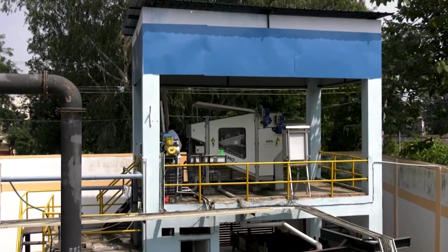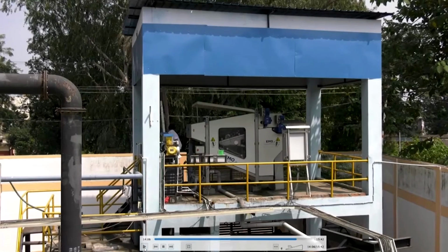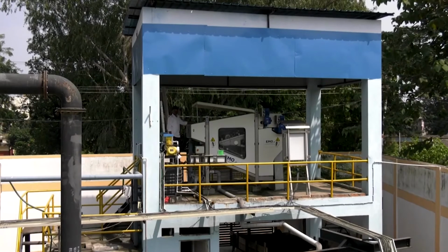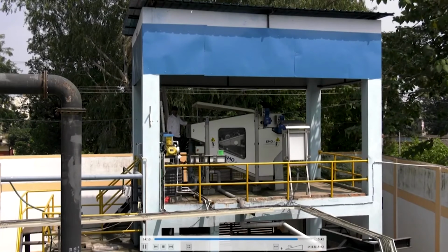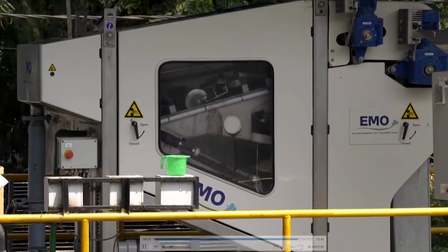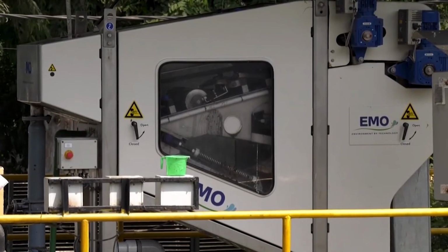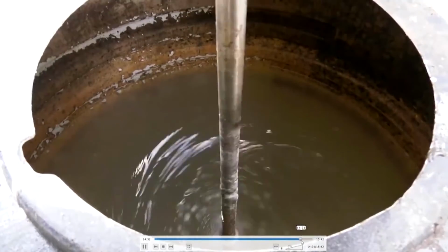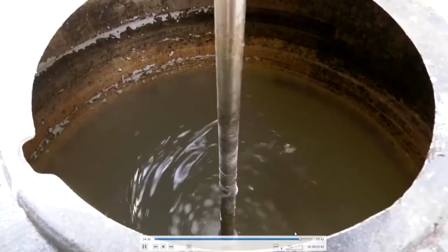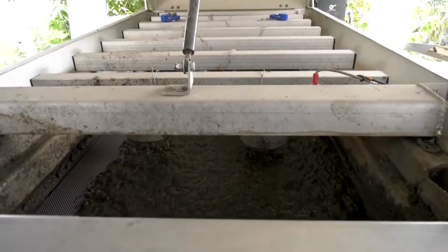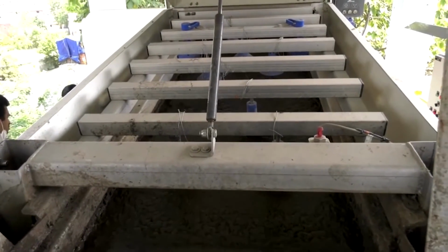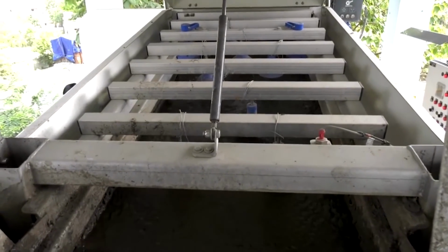We also talked about the sludge, the settled sludge, the microbes. What are we going to do with that? We need to also treat that. First you want to remove much more water from it. So you have this dewatering equipment here, and the polyelectrolyte is added to the settled sludge, not to the whole water. Polyelectrolyte is added so that bigger flocs are formed, and then the sludge goes through the dewatering equipment or machine.